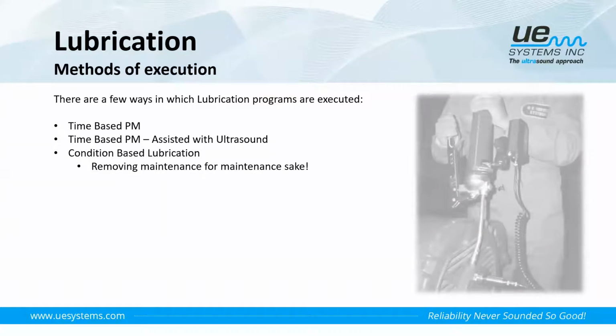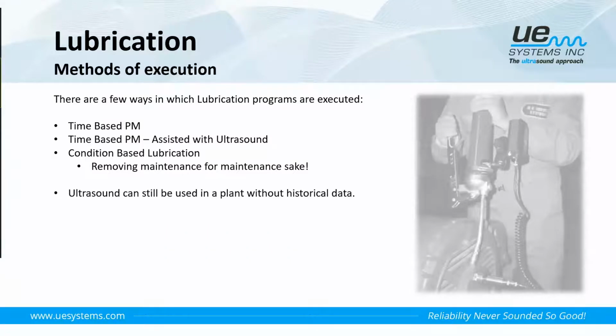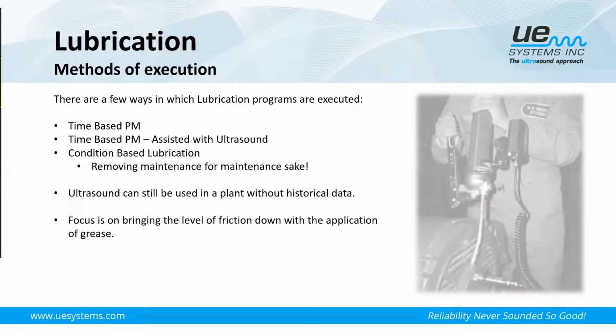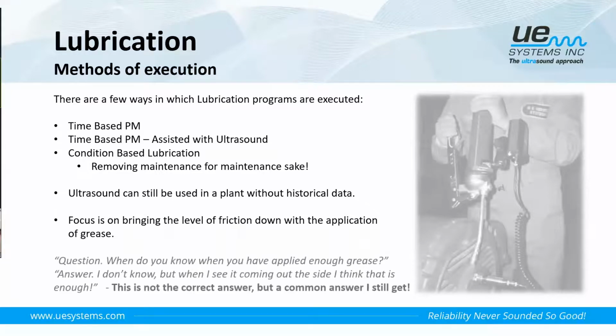It's kind of trying to find ways to remove maintenance for maintenance sake. Do we need to lubricate those bearings all the time? Does it need it? Even if we don't have historical data on our plant, we can still use ultrasound to help us with our lubrication practices. The focus is on bringing the level of friction down with the application of grease. As we know, friction produces ultrasound. So as we get an increase in friction, we start to see an increase in ultrasound. By applying grease, that friction will reduce and the sound should go down.